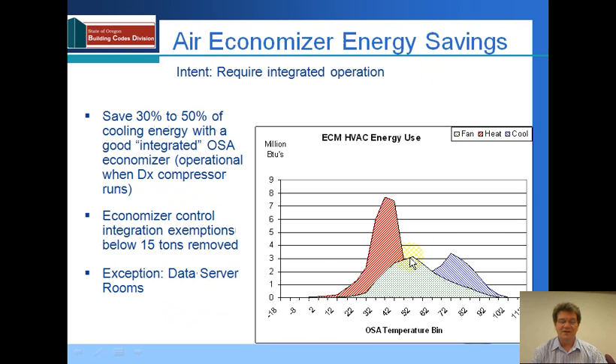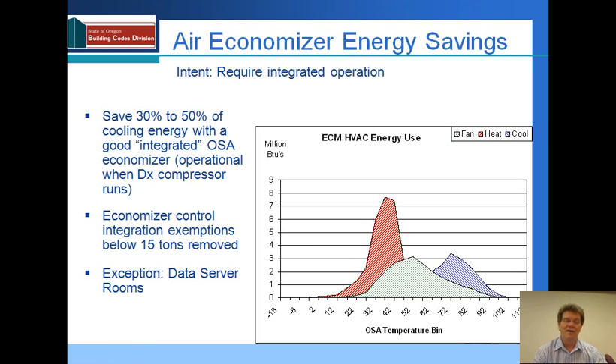As we look at the graph, we've taken a big chunk out of the cooling load, perhaps 30 to 50 percent, by using the outside air instead of the mechanical cooling when it is effective. In the new code, the economizer control integration exemptions that used to exist under 15 tons have been removed. There's an exception for data server rooms.